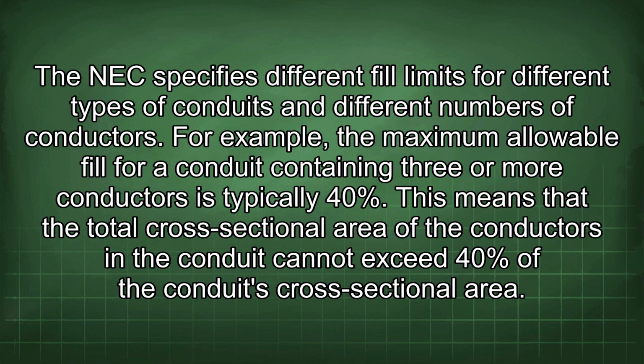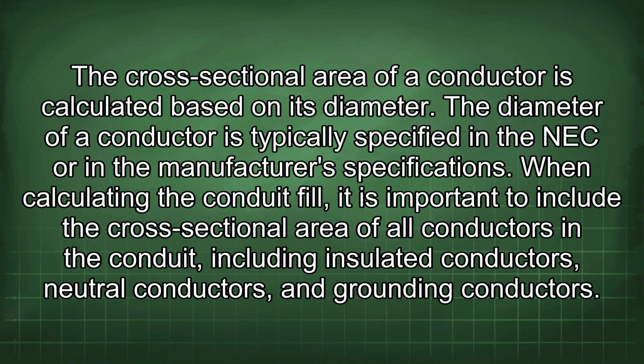For example, the maximum allowable fill for a conduit containing 3 or more conductors is typically 40%. This means that the total cross-sectional area of the conductors in the conduit cannot exceed 40% of the conduit's cross-sectional area. The cross-sectional area of a conductor is calculated based on its diameter. The diameter of a conductor is typically specified in the NEC or in the manufacturer's specifications. When calculating the conduit fill, it is important to include the cross-sectional area of all conductors in the conduit, including insulated conductors, neutral conductors, and grounding conductors.